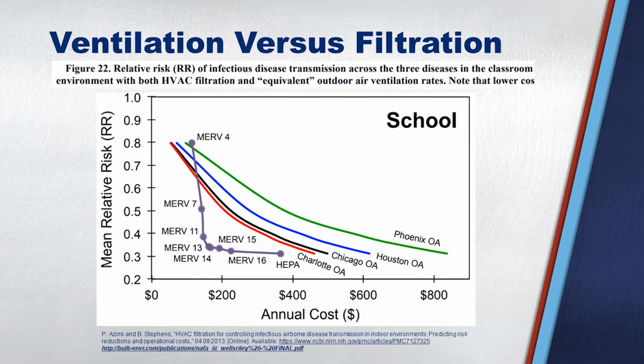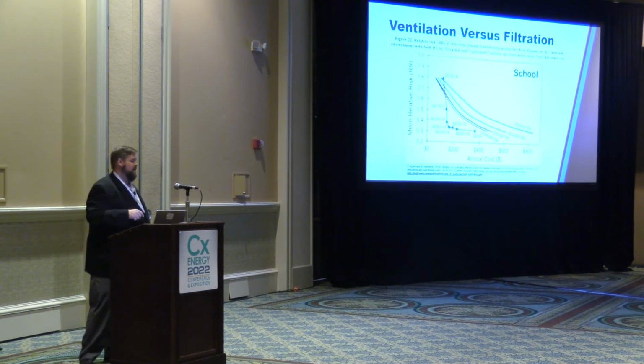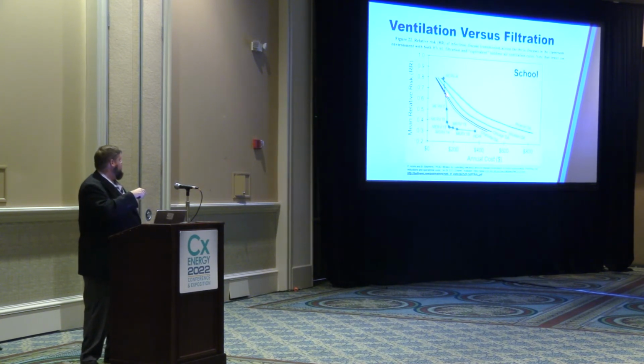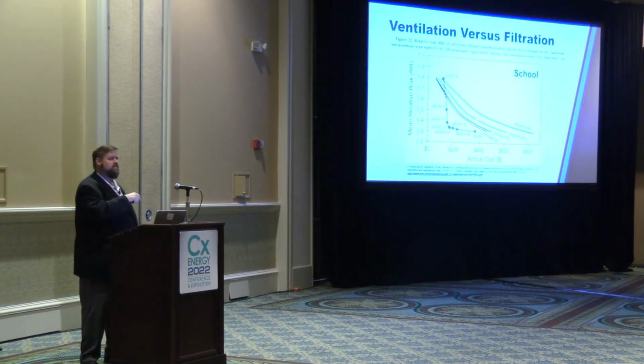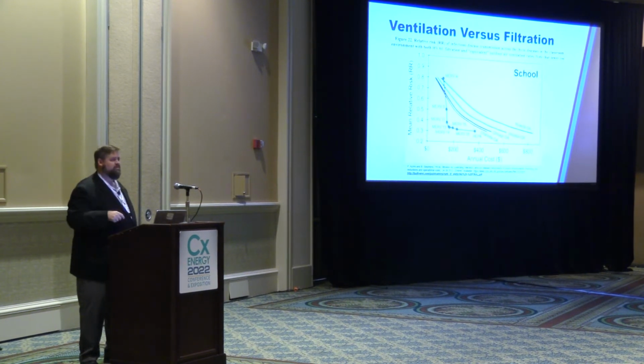Well, lo and behold, a study by Azimi and Stephens, and they looked at this, and it's like 2013 range, so these are different costs, but from a standpoint is you've got mean relative risk on your left-hand side, you've got the annual cost across the bottom, the gray line coming down is your filter, hey, MERV 13, kind of that point of diminishing returns, but then you have different cities, different weathers. We would call us Houston, and so at a MERV 13 level, you can see I'm under 200, but with outside air to do the same impact, I'm 580.